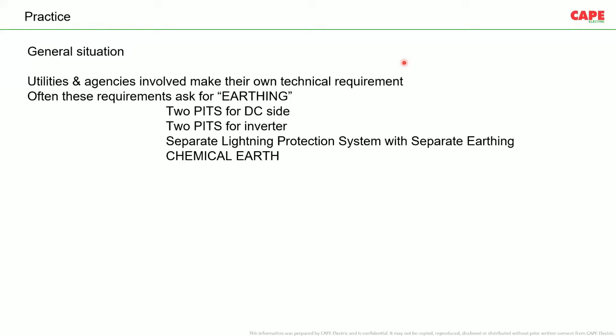Solar PV, more than shock protection, fire is a big issue. In a lot of places fire accidents are happening, so we have to be very careful. People may think that, okay, it is a rooftop, some fire, nothing happens to the building. It is not like that. Sometimes the inverter which is inside a building also can catch fire. So utilities and agencies involved make their own technical requirements. Often the requirements ask for a kind of earthing. I'm not trying to cover the other subjects. I'm trying to focus on earth fault protection, or protection against fire during earth fault.